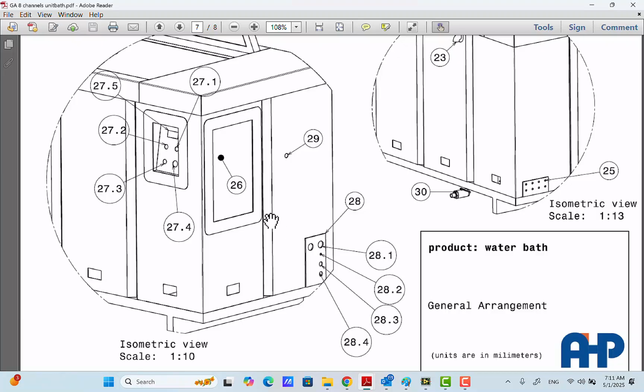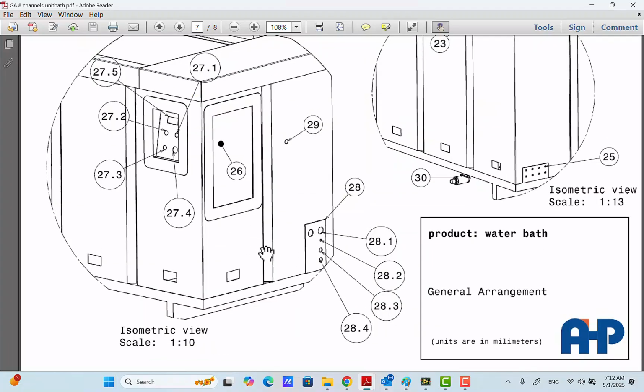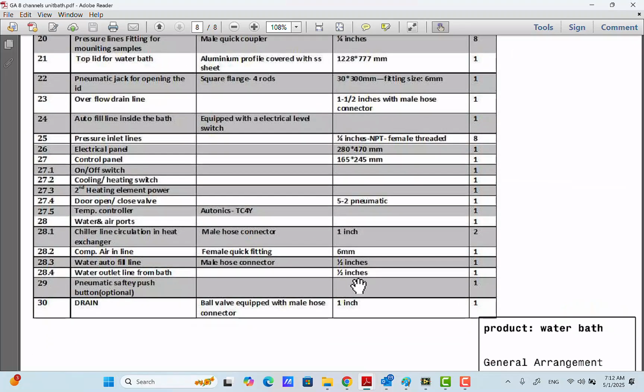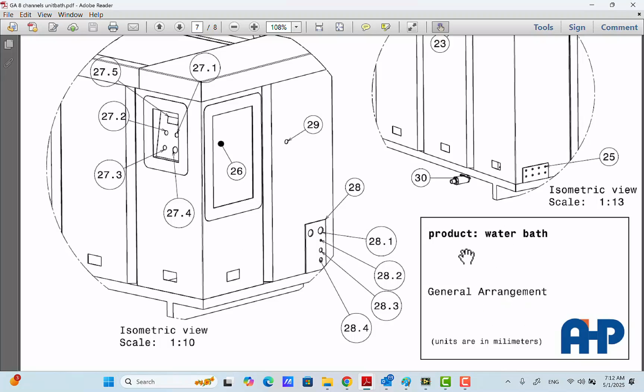In any case, suppose that the laboratory room temperature is higher than 30 degrees, for example, and you want to reduce the temperature to do the tests at 20 degrees centigrade. Turn this key on the panel to the left side, to cooling, and set the temperature on the display to 20. In that case, this controller will activate the chiller. There is a connection between the tank and the chiller, and the order will go to the chiller to start working. The cold water will be circulated using these two connections for the chiller, inside the heat exchanger inside this tank that is located on the right side of the tank, and will reduce the temperature to the requested, in this case, 20 degrees centigrade.